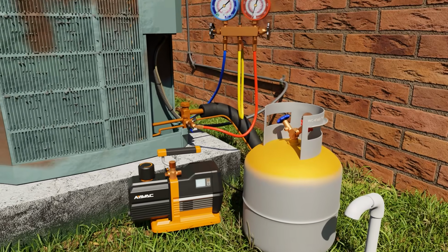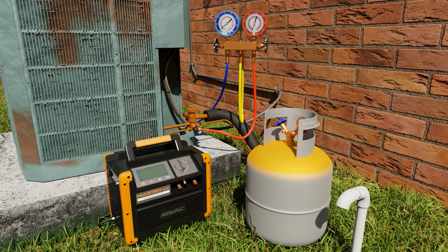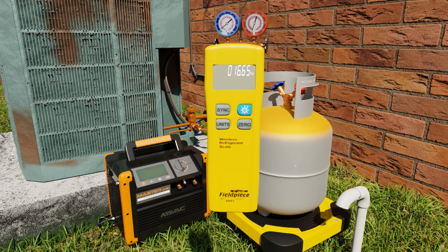Next, you close off the tank and disconnect your vacuum pump. You're going to save the vacuum pump for pulling the vacuum on the system later. Now bring your recovery machine and refrigerant scale. You can see that I put the tank on the scale and zeroed out the scale to begin receiving refrigerant into the tank.